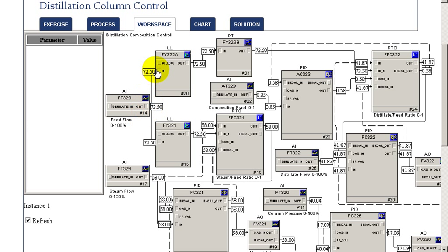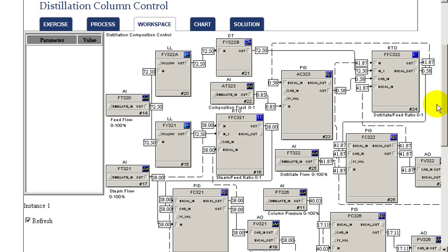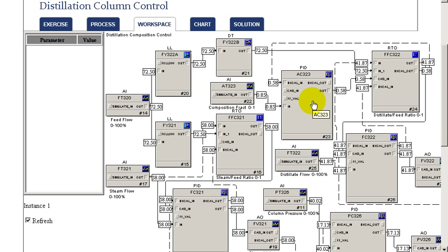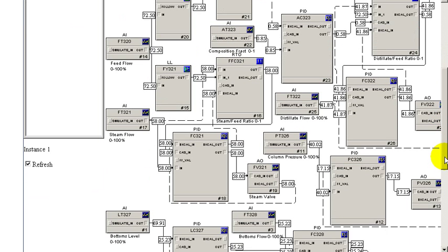Also based upon that flow rate after dynamic compensation, we're going through a ratio control to set the distillate flow. The set point of that ratio controller is determined by a PID that is using the composition of the light material in the overhead.